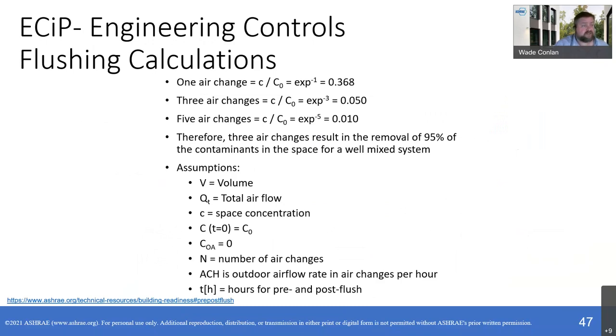So we'll get into the flushing calculations. This is the main piece for getting in the new materials. Bill discussed this already, which is three air changes. We're assuming it's steady state, with no contaminant being generated. So if I change the building volume three times, I end up with 0.05 left, which means 95% removal. Now, if I have a different space that has a lot higher risk, let's say you have a cafeteria in your area, or other spaces like a gymnasium, you might want to go five air changes, which gets you the 99% removal. So that's part of adjusting the risk for your level. But as a starting point, we're saying three air changes.